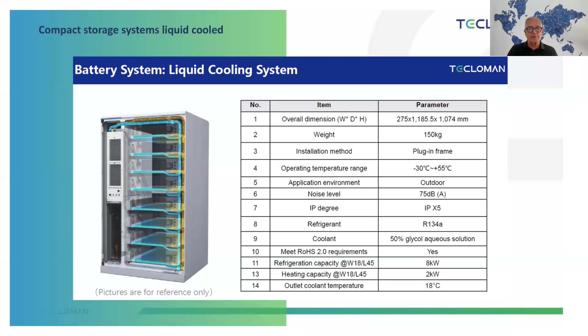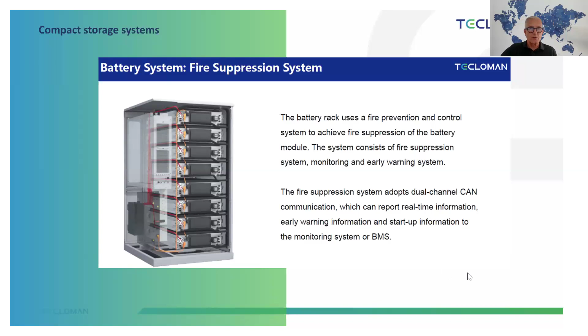And this is also a very important step for better quality of the batteries and better performance of all the storage systems. You see here also a fire suppression system. So every compact system is secured with a fire suppression system. And because of liquid cooling and also because of the lithium iron phosphate technology, it's not possible to burn it as easily as was the case in the past with nickel manganese cobalt solutions, because the fire threshold temperature in centigrade is higher on the LFP side. So this is a better solution also because of this.